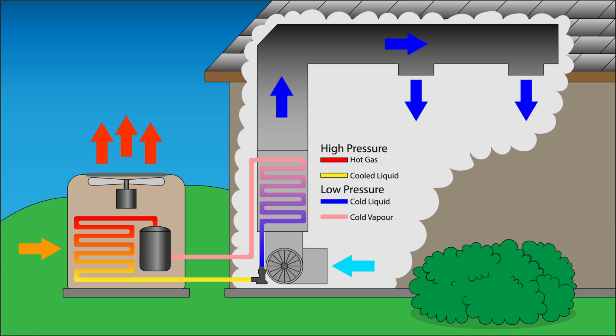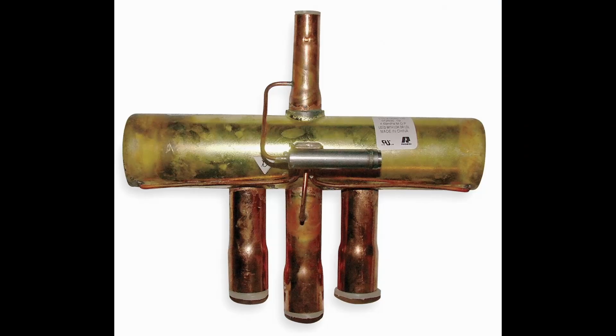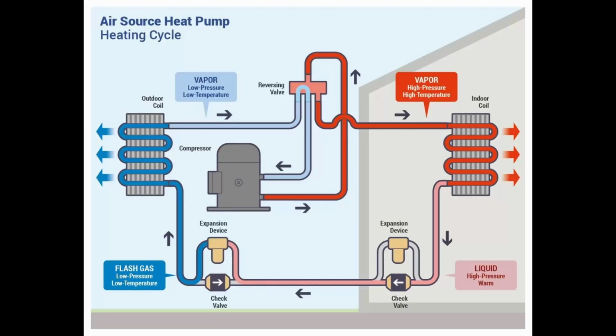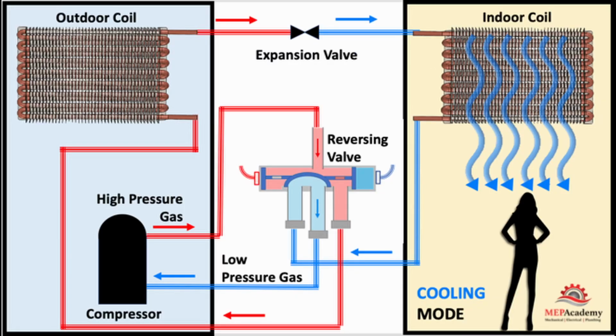That is a conventional air-to-air heat pump, but hardly anyone ever refers to a conventional cooling-only DX system as a heat pump. When you hear someone say heat pump, you should think of a reversing valve on a DX system that can provide heating or cooling. The reversing valve switches the functions of the evaporator coil and the condenser coil. In cooling mode, the indoor coil can correctly be called the evaporator coil and absorbs heat from the indoor air. The outdoor coil, which can correctly be called the condenser coil, rejects the heat to the outdoor air.